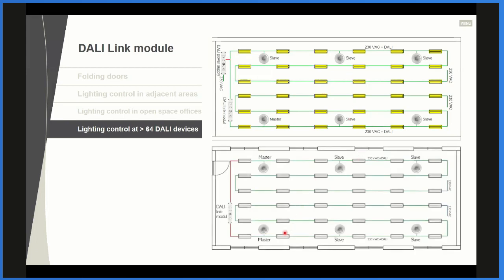It could be the sports hall here, where you have two masters instead of one, and then you don't need a power supply to supply the other half of the DALI bus in the sports hall, but you still need the DALI link module in order to have the communication between the two masters. It could also be an advantage if you have daylight control to have two master detectors here, because this master detector is controlling the luminaires according to the incoming daylight from the windows. One could be facing east, and this one could be facing west. That means we have a different incoming level of daylight during the day, so it is controlled in a much smoother way than with only one master detector.